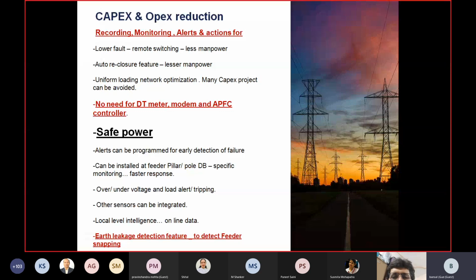So once it crossed maybe 90%, 100%, we used to either install a new transformer or augment the capacity. But we realize there are very few, maybe 10%, 5%. After the summer, we used to check every month, August, September, how many transformers crossed the value of 70%, and we used to find 10%, 12%, 15% had crossed.